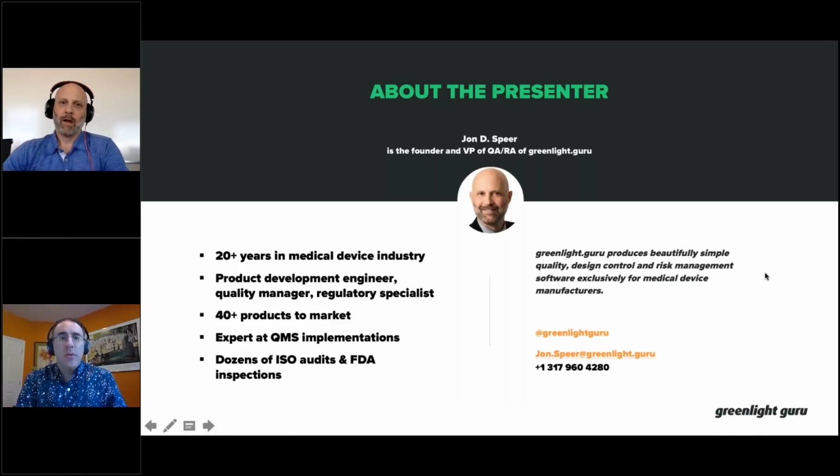That is not, I mean, there's some truth to that, but let me clarify some details around that. First of all, in the United States, if you're a medical device company, you must demonstrate and comply with FDA 21 CFR Part 820, the quality system regulations. That's the must. If you have ISO 13485 certification, that does not mean that FDA necessarily believes you to be compliant to the regulations. We're not quite there yet.